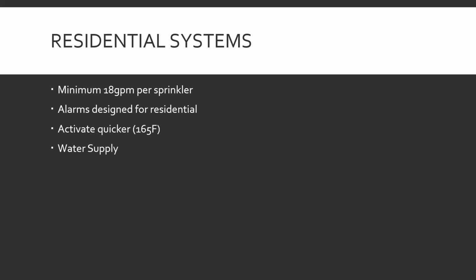They're designed to activate quicker than your standard system, so they're designed for 165. Start a little earlier, maybe protect occupants a little quicker. It's all about life safety. If it goes off at a lower temperature, that's potentially longer that people have to get out of the house or have the fire department show up and rescue. The residential water supply could be connected to the normal city water supply. They live in the city, they get their water from the water main just like every other appliance and source of demand of water in their house.